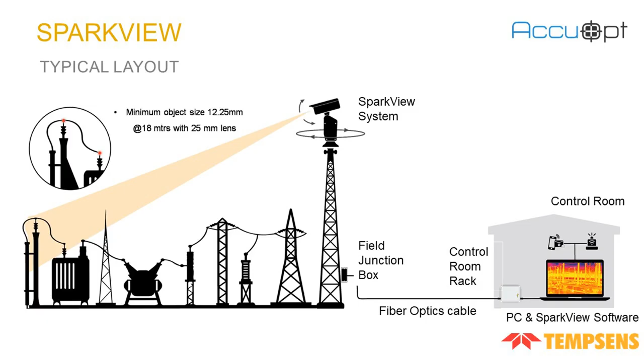This is the typical layout for the SparkView system. The SparkView will be installed at a 2 to 3 meter height from the monitoring component to have a clear line of sight. As you can see in the image, the hotspot is detected with minimum object size of 12.25 mm at 18 meters distance with 25 mm lens. This is a 384 resolution camera.